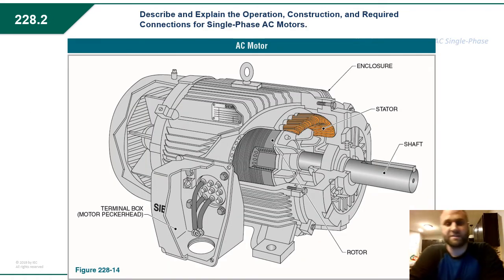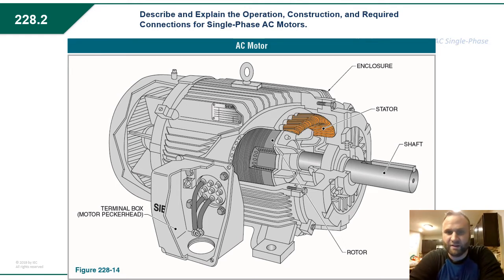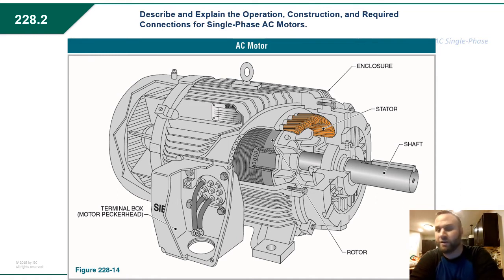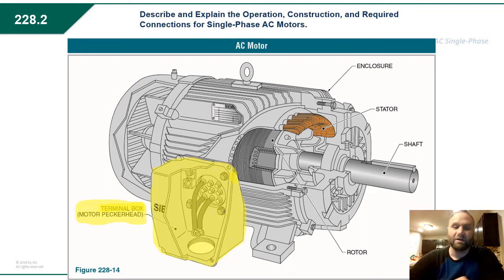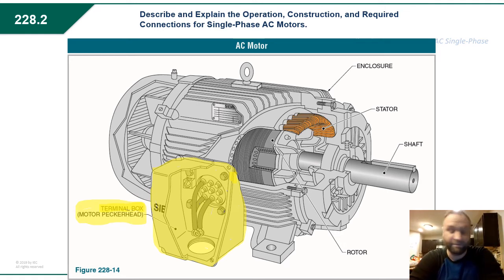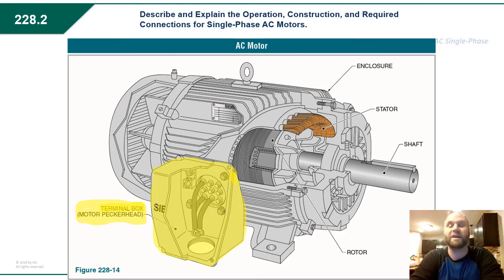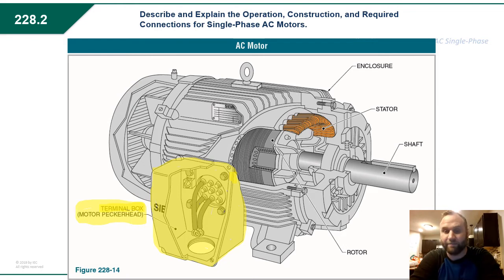Let's look at AC motors. An AC motor runs on alternating current, so we don't need to change direction like we did with DC motors through a commutator — this is based solely on induction. The terminal box, also known as the motor pecker head, is where the termination is made to the AC circuit coming in, and these leads are directly connected to the stator in the motor. The pecker head leads go directly to the stator, which creates a fluctuating magnetic field. It also goes to the field windings — the run winding and the start winding.